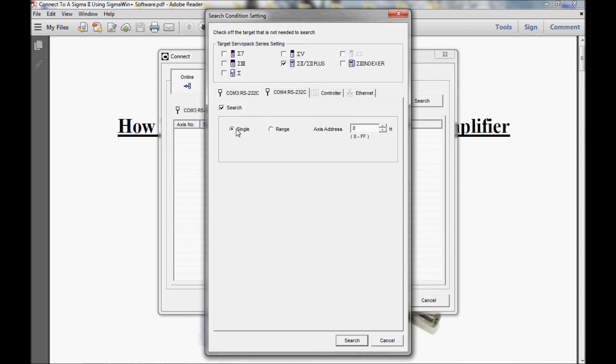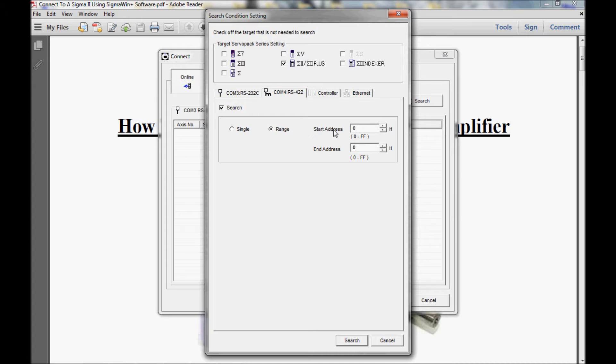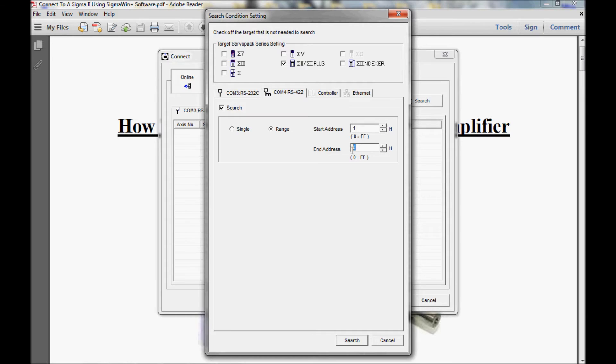As you can see, it did not find the servo pack. I'm going to click OK, go back to search, place my check mark here, and that brings this field back into an active state. Now I can search for a single axis address, which I can change from 0 to FF. But I'll leave it 0 because my amplifier is set to factory default settings. I can also choose this radio button here, which will allow me to search a range of addresses. I would place my starting address here, say starting address of 1, and an ending address of, say, 7.